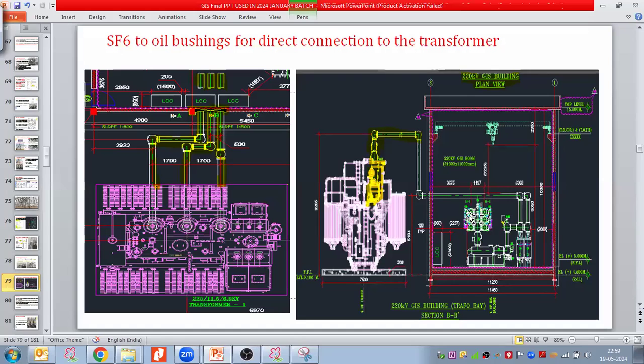So now here we have the GIS substation, the GIS model placed here, the duct coming out, and it is terminating at the gas to oil bushing. This gas to oil bushing is very costly, so for that reason try to avoid this. But if you don't have the space, then it is the only choice, right?